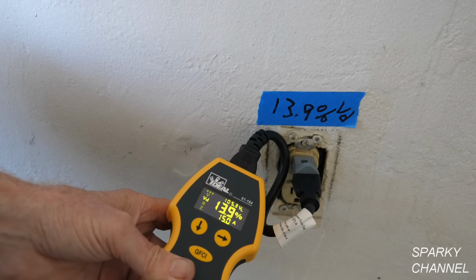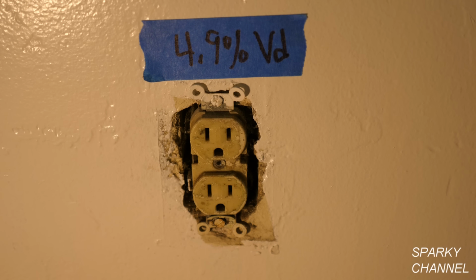15 amps. This receptacle here, this is the first one I looked at. It's the one that's closest to the main panel, and it has the least voltage drop at 15 amps. If I was a betting man, I would bet that this is the most upstream receptacle of the 7.